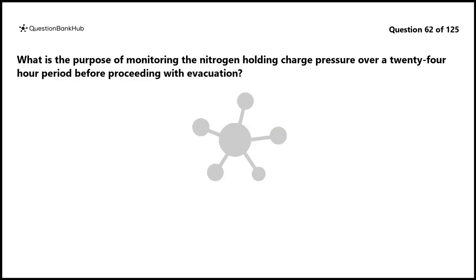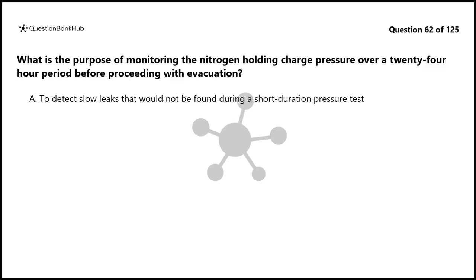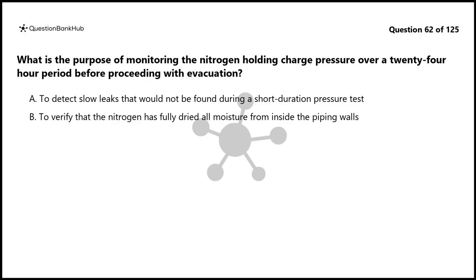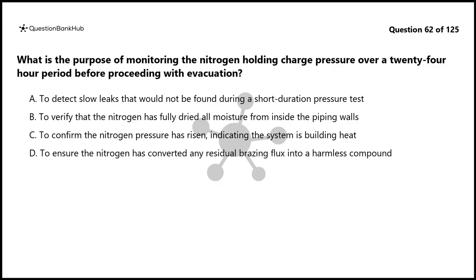Question 62. What is the purpose of monitoring the nitrogen holding charge pressure over a 24-hour period before proceeding with evacuation? A. To detect slow leaks that would not be found during a short-duration pressure test. B. To verify that the nitrogen has fully dried all moisture from inside the piping walls. C. To confirm the nitrogen pressure has risen, indicating the system is building heat. D. To ensure the nitrogen has converted any residual brazing flux into a harmless compound.